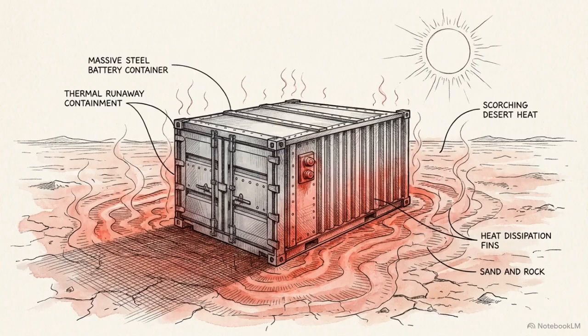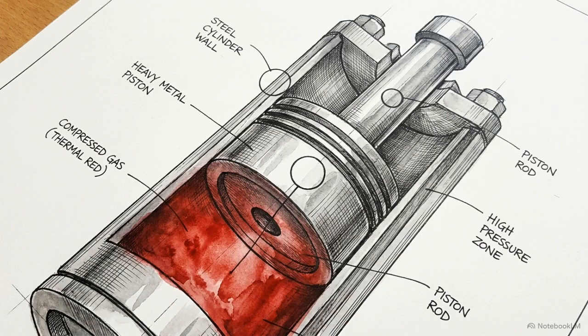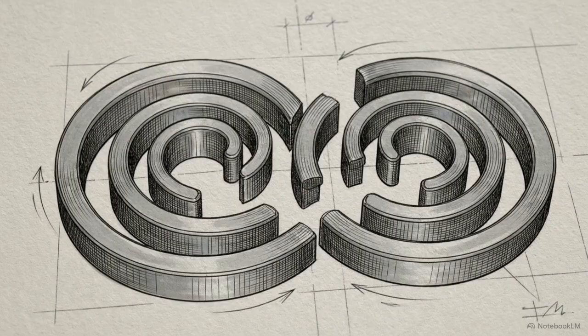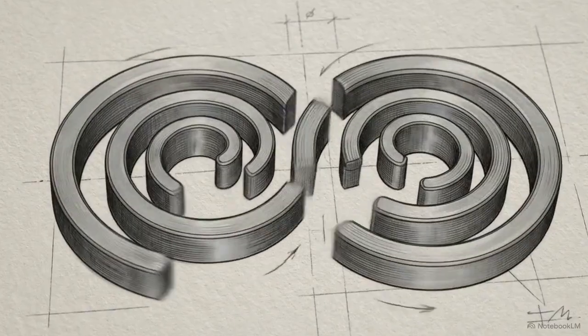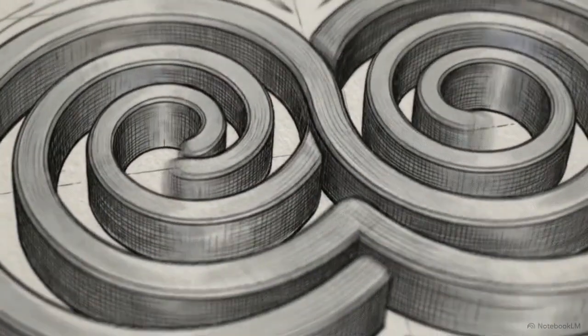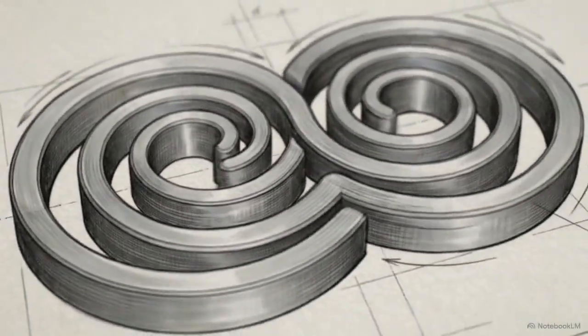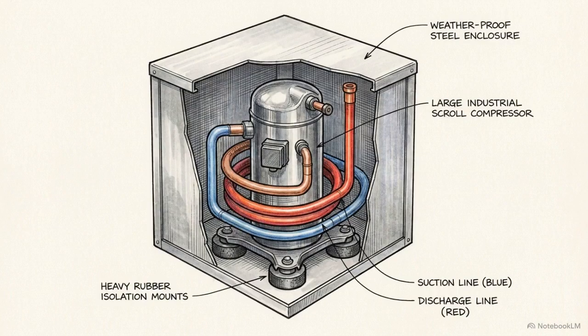To reject this heat into the outside atmosphere, the gas must be hotter than the ambient outdoor air. The system achieves this by mechanically compressing the gas, which forces its pressure and temperature to spike simultaneously. The mechanism responsible for this pressure spike is the scroll compressor. Industrial energy storage relies almost exclusively on this technology. Their interlocking spiral design provides strict capacity control and high durability, allowing them to handle the constantly fluctuating thermal loads of a dynamic power grid.